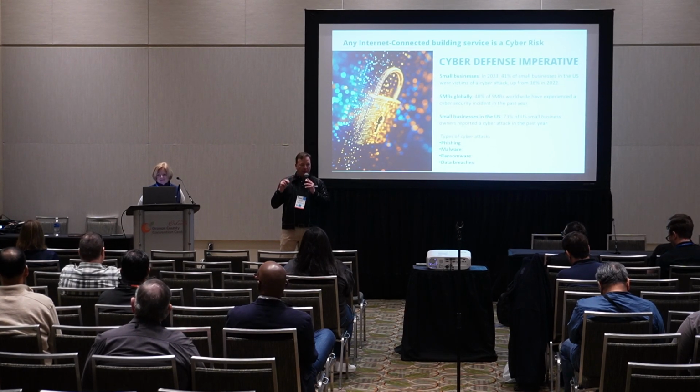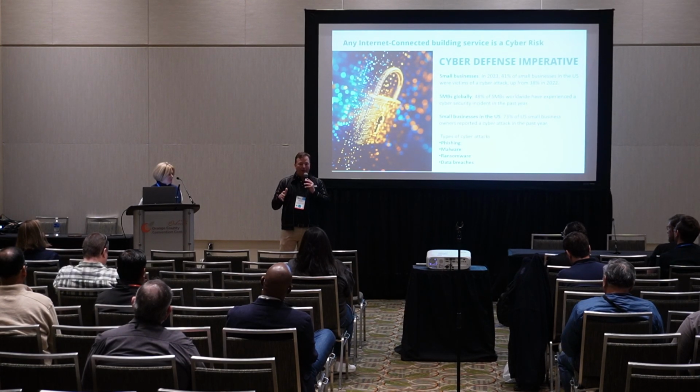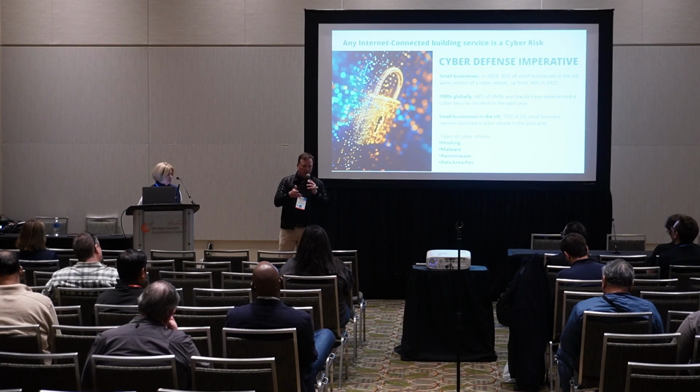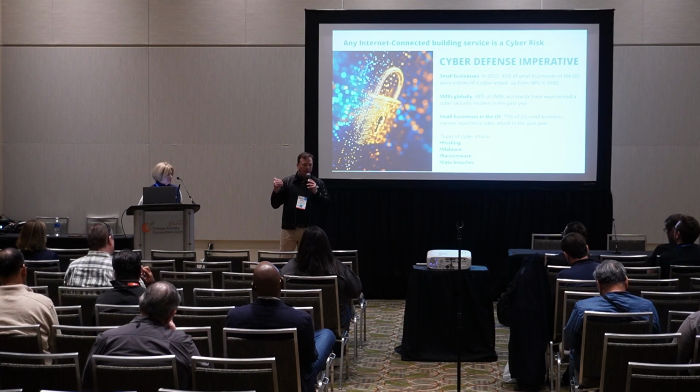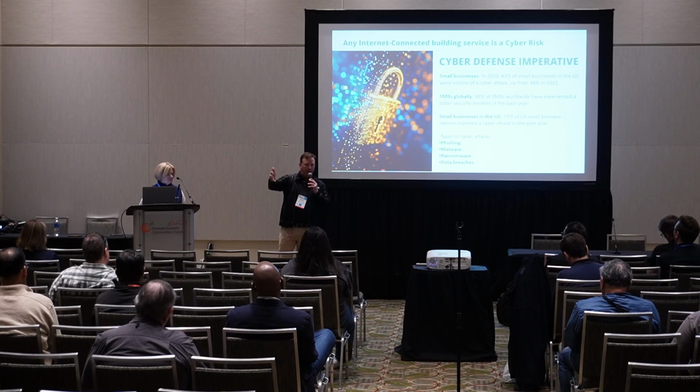So if it's just BACnet IP that you're putting on like a college network, there's going to be 1,000 kids on that campus that can decode BACnet IP and mess with set points. And BACnet describes where the set points are. So when you deploy on an owner's network, we need to make sure that you have an encrypted method.